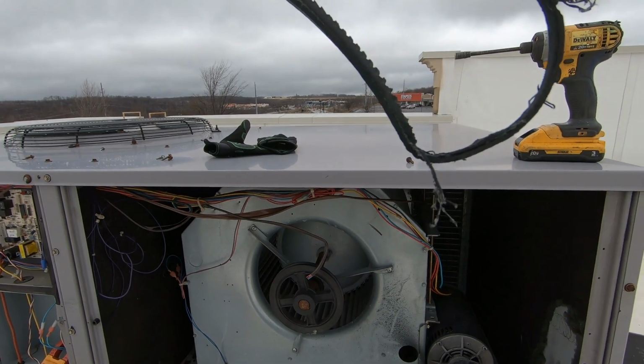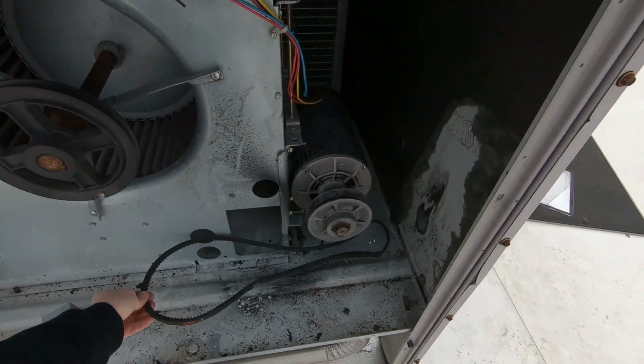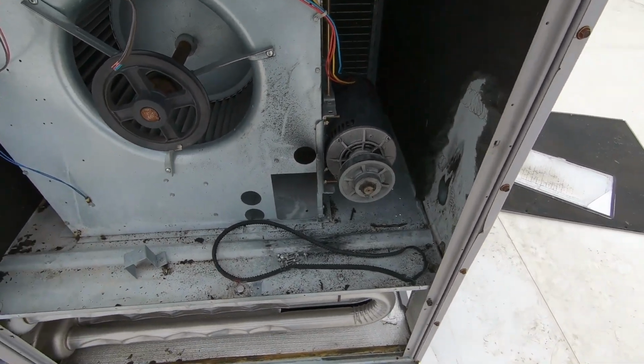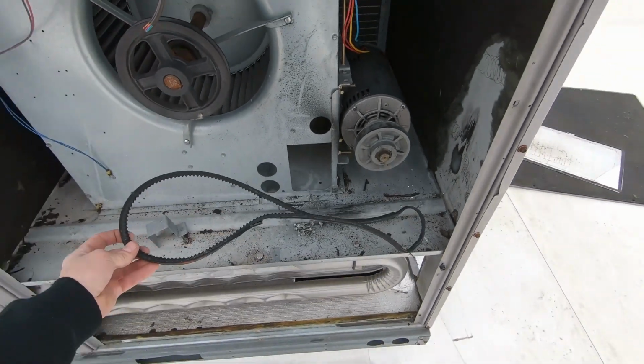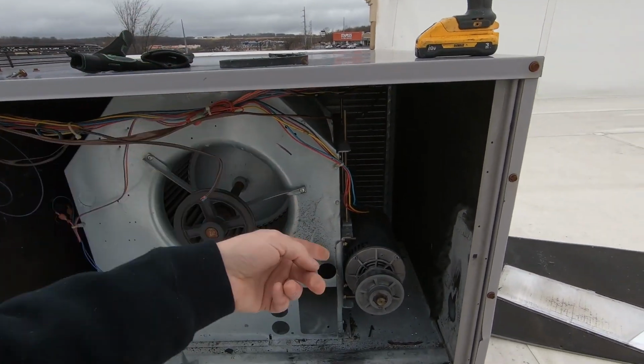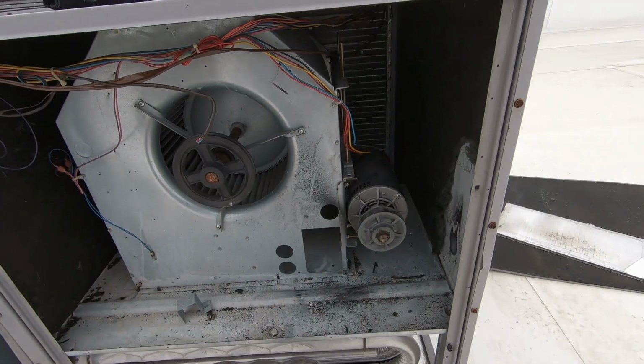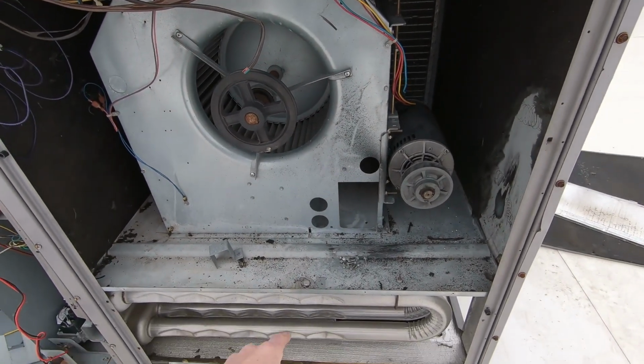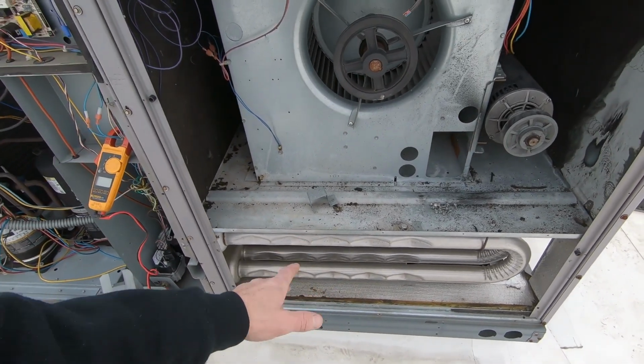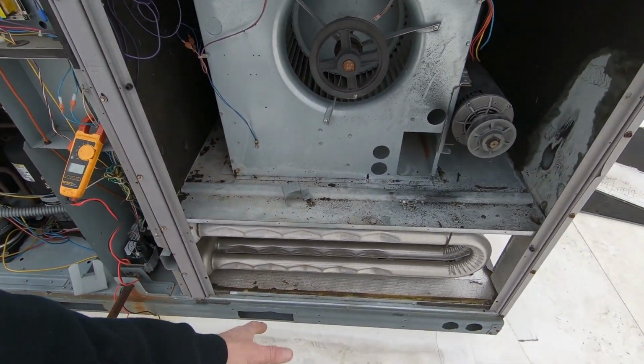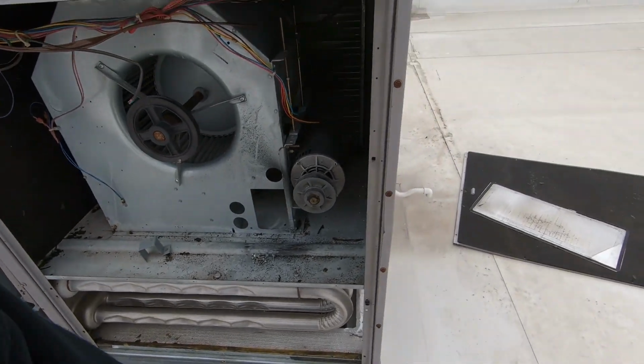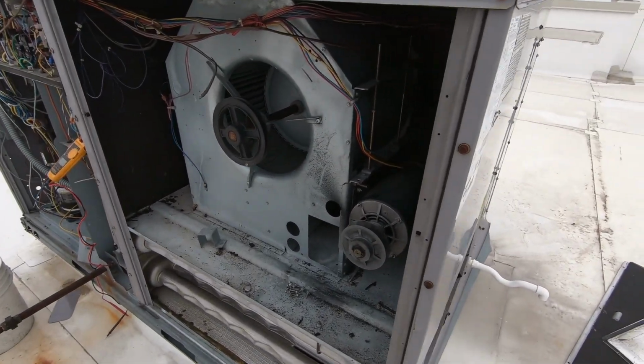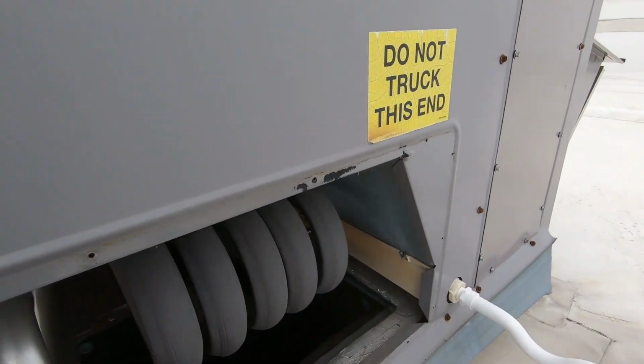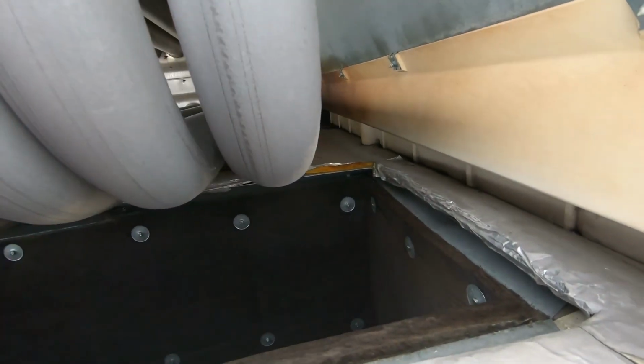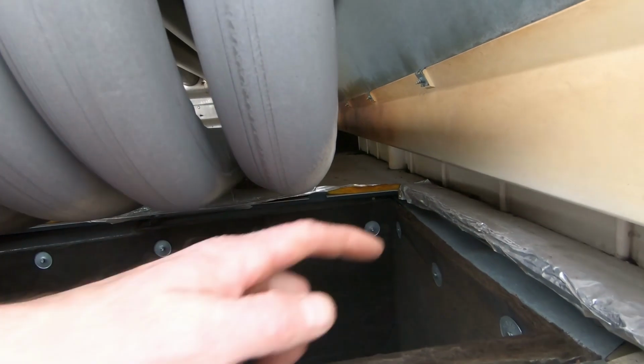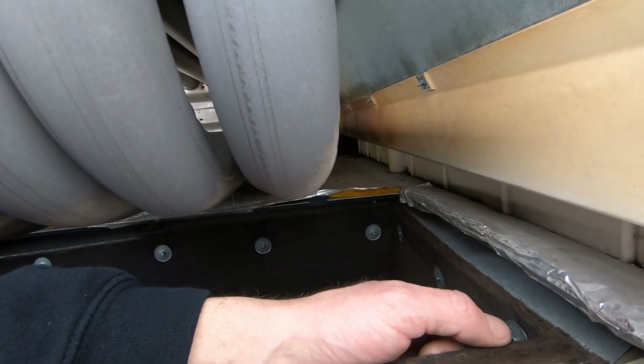Obviously chewed the belt up, but the belt was down here when I got here. So I don't think the smoke smell and the smoke that actually filled the store was from the belt. I think the motor cooked. It probably cooked because of the intense heat from the heat exchanger never shutting off. You know, the heat never shutting off. This heat exchanger had to have been glowing red. I mean, glowing red. You can see here that it melted and singed the condensate pan.